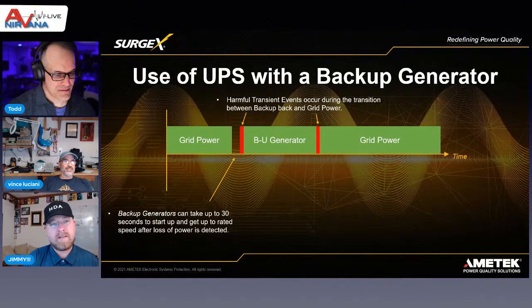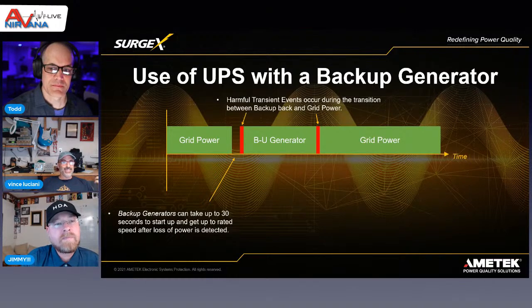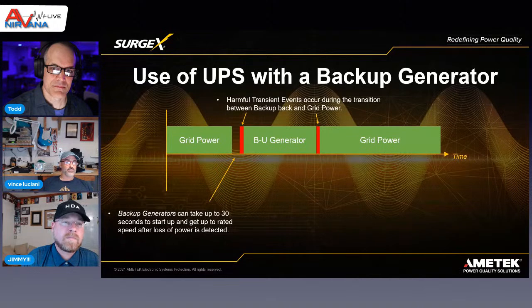UPS battery backup is like 20 to 30 minutes. We can put enough battery capacity on there, and there are battery systems out there intended for longer, but those are walls and walls of batteries to get you there. What you really want is a generator on premises for your consistent source of backup energy, because you're running off of a fossil fuel, most likely natural gas or diesel, depending on where you're located. Let the generator do the backing up of the power, but let us be the thing that cleans it up. So there's two parts to the generator scenario.